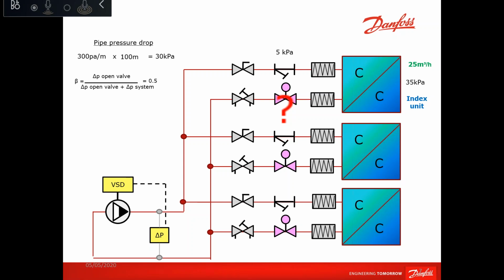What we need to have is an authority of 0.5, which means that the pressure drop across the control valve should be equal or higher than the pressure drop across the coil and the remaining of the circuit. In our case, we have 300 Pascal per meter resistance on the pipe, which is 30 kPa. We have 5 on the strainer, and we have 35 on the coil. So if we want to achieve an authority of 0.5, we need the two-way valve size selected at 70 kilopascal to achieve a 0.5 authority, which is the case in this example.